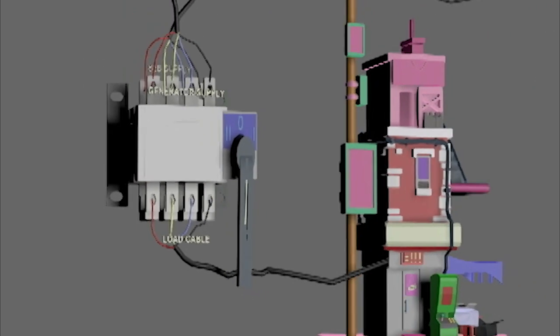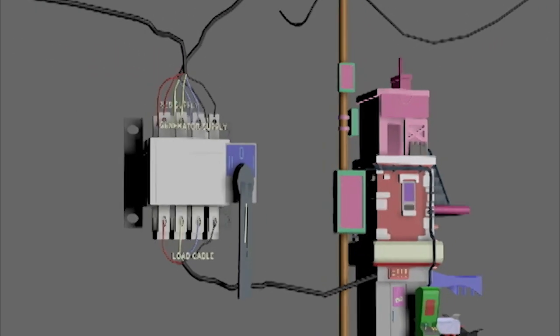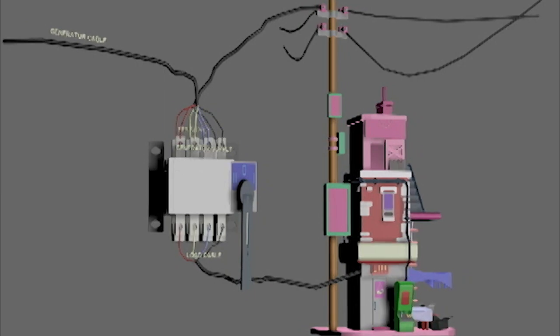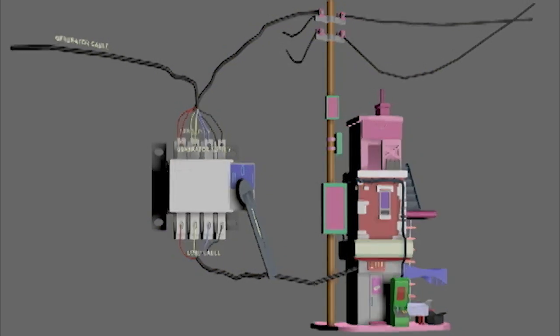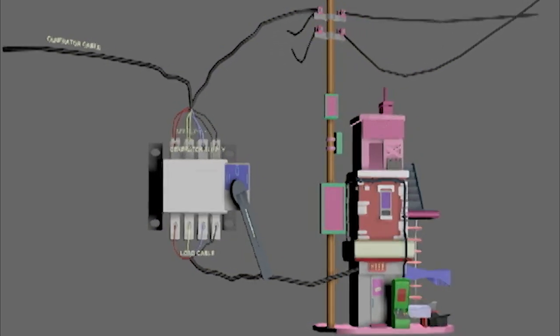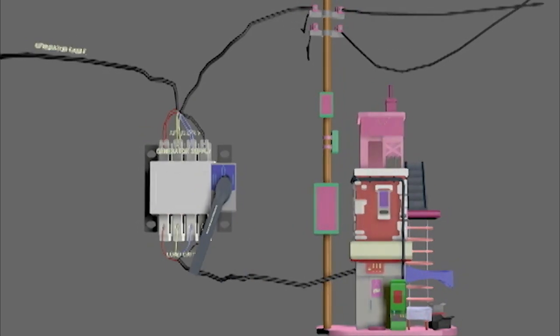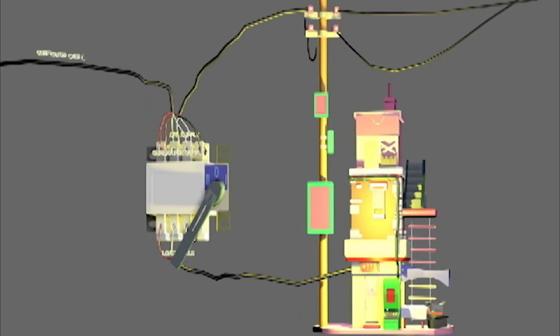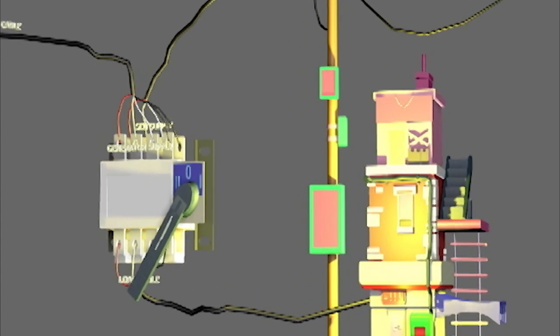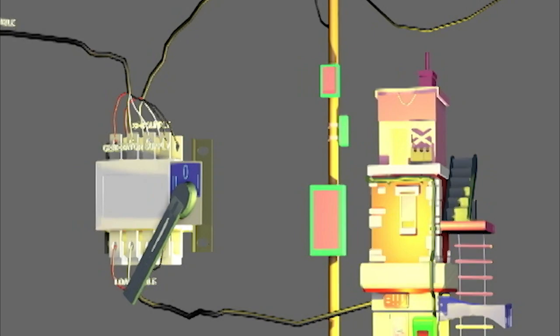Here the handle position is at 0 and the building is disconnected from both power sources. As the handle is moved to position 2, the building gets power from the state electricity supply. Now if there is a power failure, the handle is moved to position 1 and the building gets power from the generator supply. So the changeover switch is used to select the power source to supply power to the load.